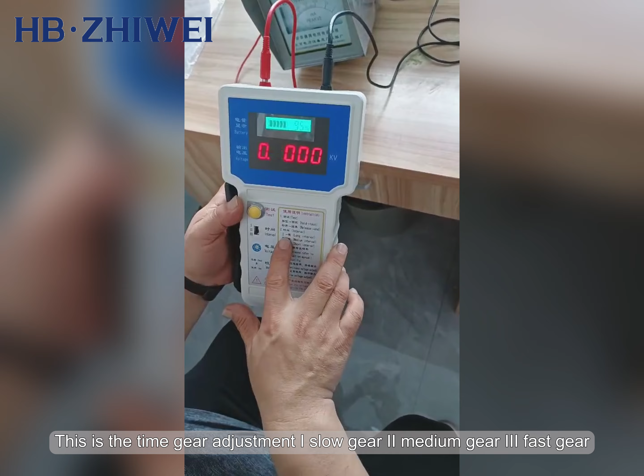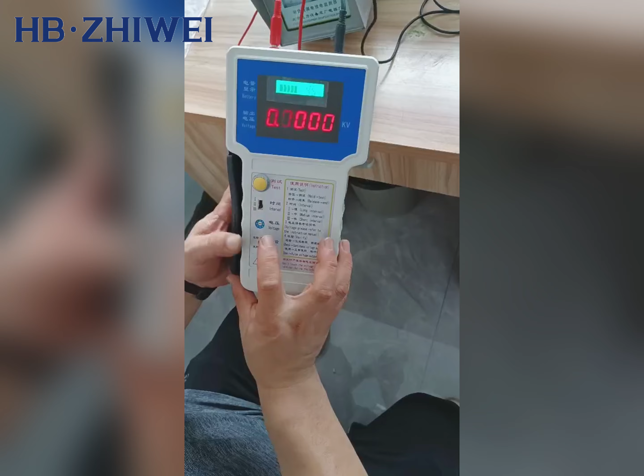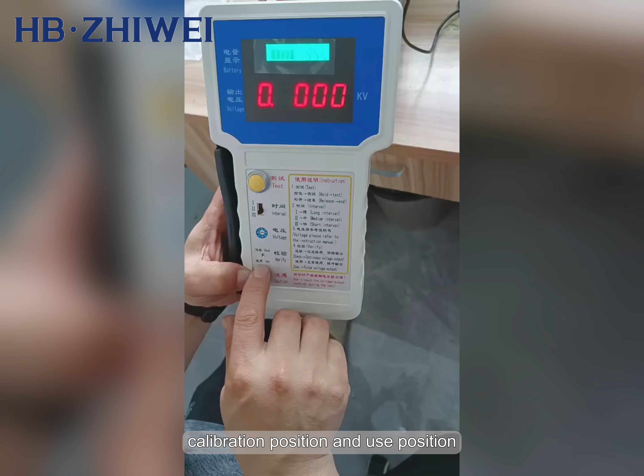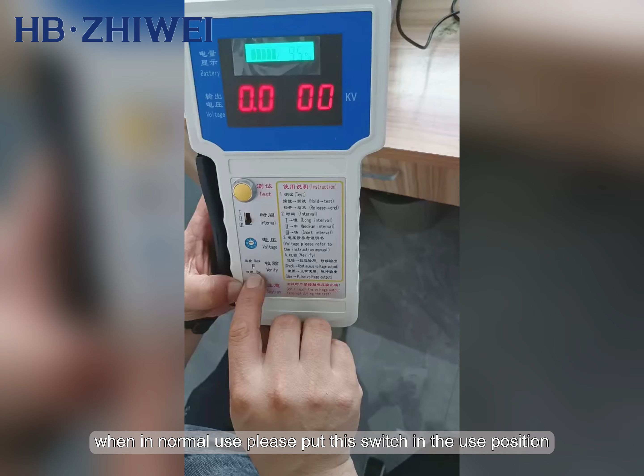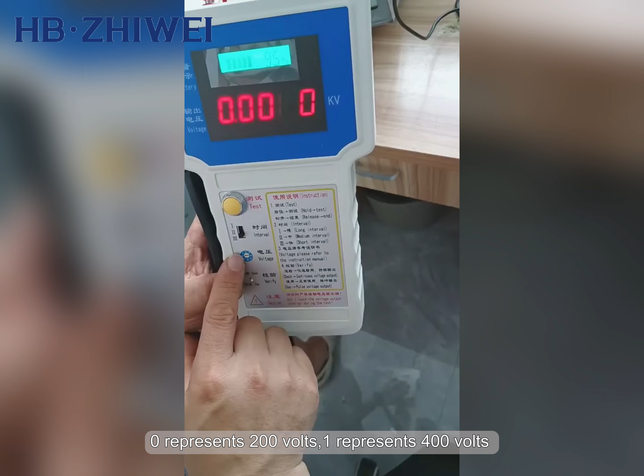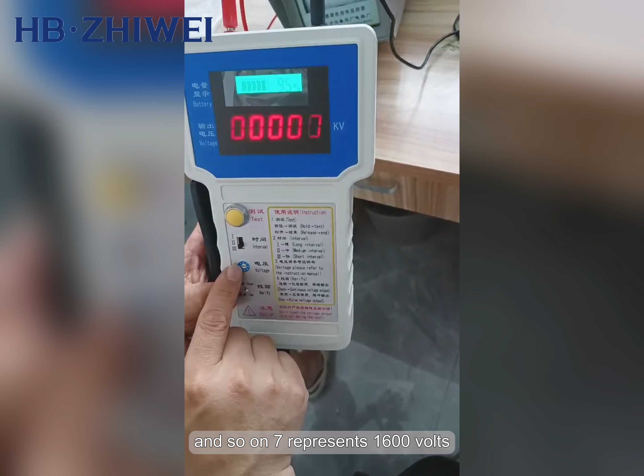This is the time gear adjustment: 1 slow gear, 2 medium gear, 3 fast gear. Here we choose 3 gear. This is the calibration switch, which has 2 positions: calibration position and use position. When in normal use, please put this switch in the use position. This is the voltage level. 0 represents 200 volts, 1 represents 400 volts, and so on. 7 represents 1600 volts.